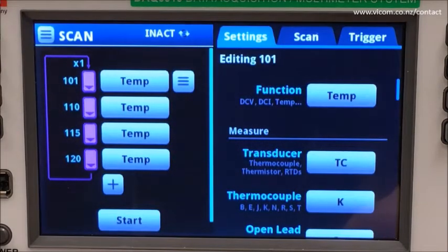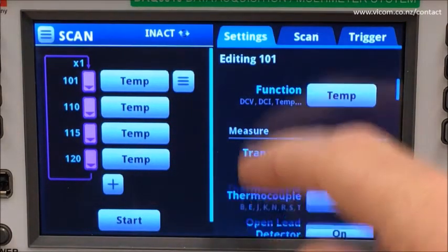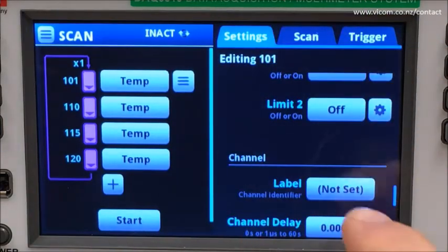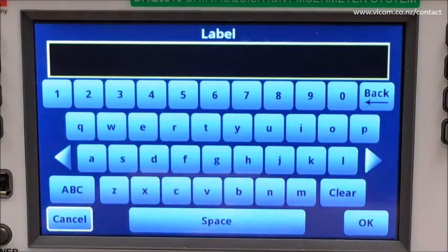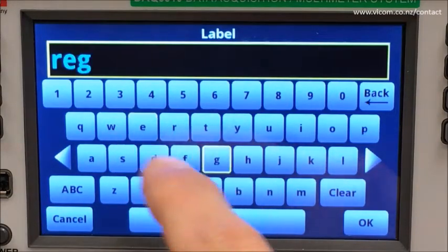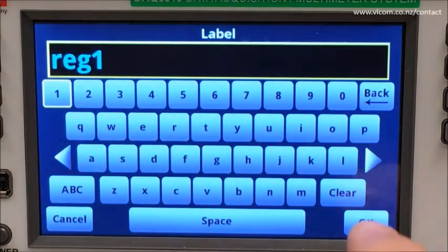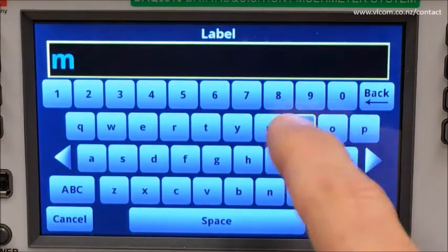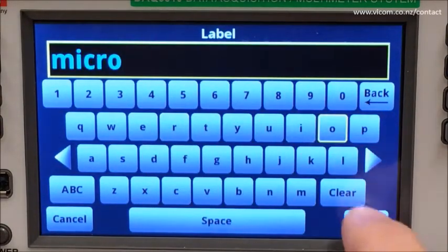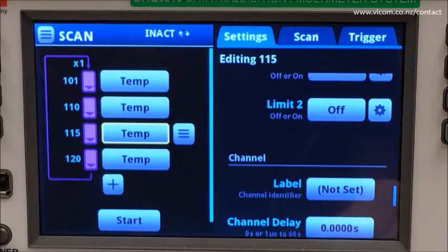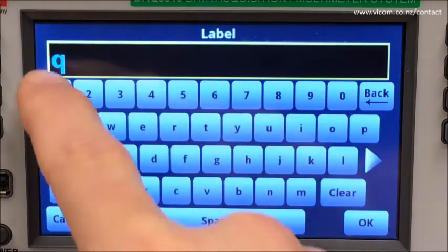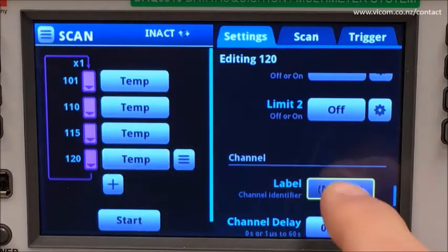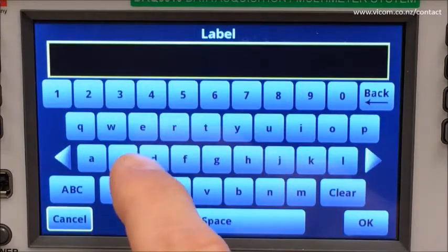I mentioned setting labels for each channel — let's do that now. Channel 101 will monitor a regulator, channel 110 will monitor a microprocessor, channel 115 will monitor a transistor in the charge control circuit, and channel 120 will monitor the enclosure.